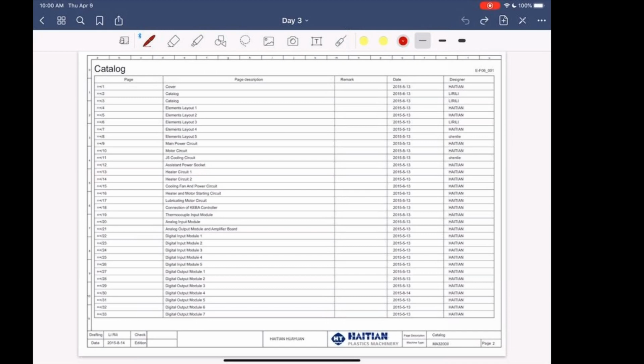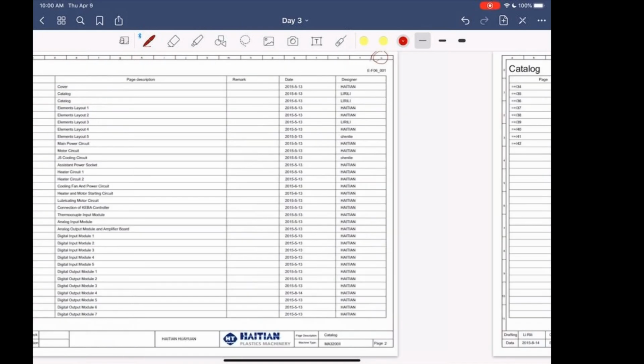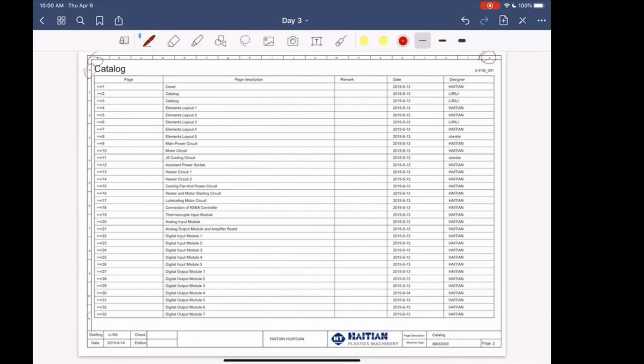And the way these prints are laid out, it's in a grid format. So you have A to U, sorry, and 0 to 11. So anytime you see a reference, you just use the grid. It's like a mapping type of format. You can use just the grids as finding your location of where your component that you're looking for is.